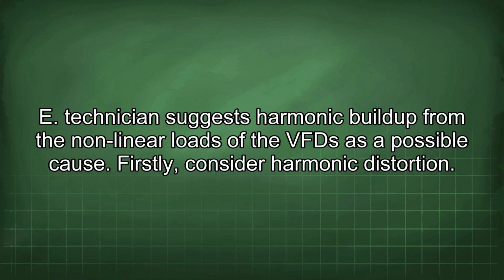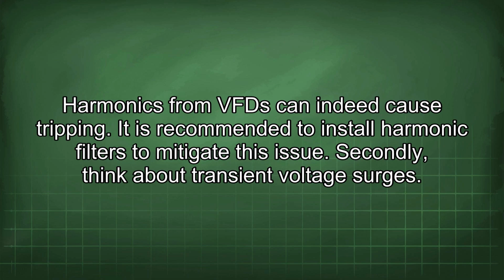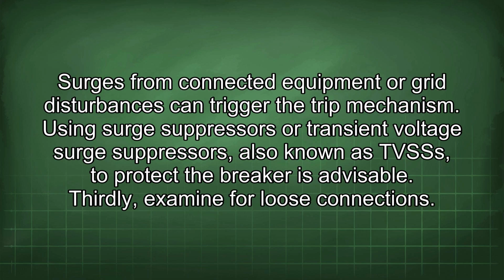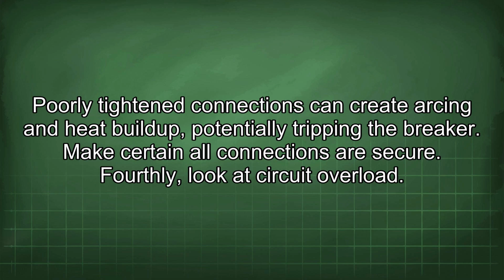Firstly, consider harmonic distortion. Harmonics from VFD can indeed cause tripping. It is recommended to install harmonic filters to mitigate this issue. Secondly, think about transient voltage surges. Surges from connected equipment or grid disturbances can trigger the trip mechanism. Using surge suppressors or transient voltage surge suppressors, also known as TVSSs, to protect the breaker is advisable. Thirdly, examine for loose connections. Poorly tightened connections can create arcing and heat buildup, potentially tripping the breaker. Make certain all connections are secure.